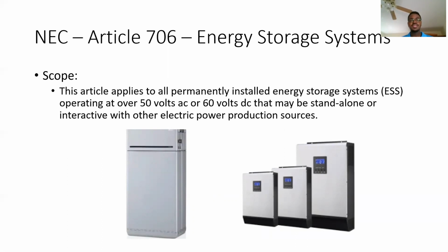So the scope is that this article applies to all permanently installed energy storage systems operating over 50 volts AC or 60 volts DC that may be standalone or interactive with other electrical power production sources. So these are two images of energy storage systems and different batteries that are included within the energy storage system scope.